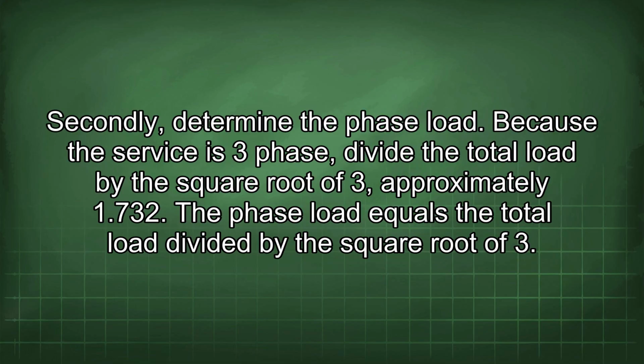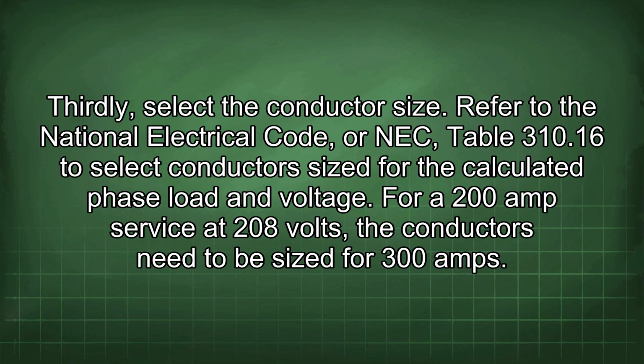Secondly, determine the phase load. Because the service is 3-phase, divide the total load by the square root of 3, approximately 1.732. The phase load equals the total load divided by the square root of 3. Thirdly, select the conductor size. Refer to the National Electrical Code, NEC, Table 310.16 to select conductor size for the calculated phase load and voltage. For a 200 amp service at 208 volts, the conductors need to be sized for 300 amps.